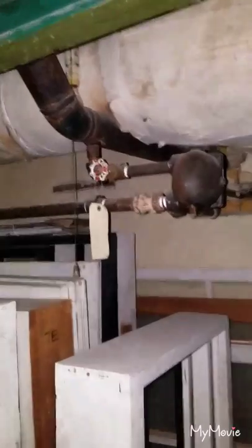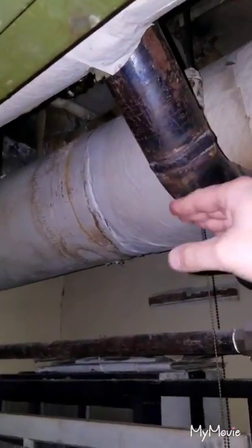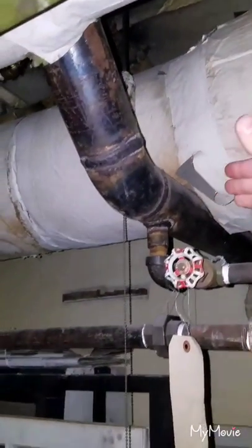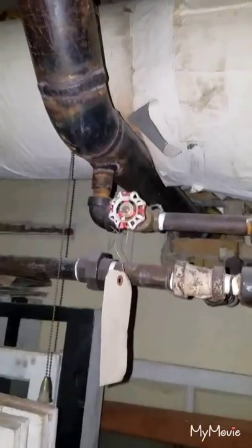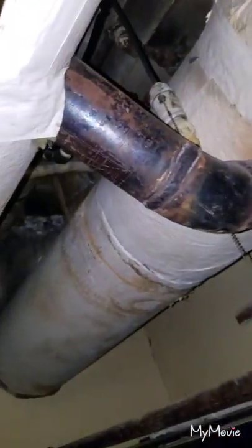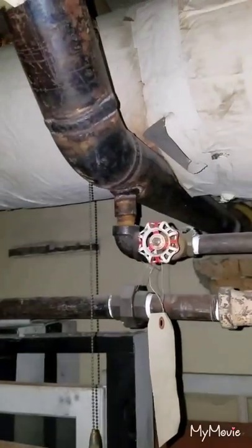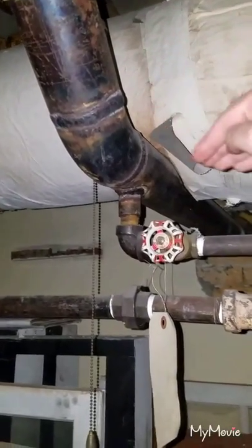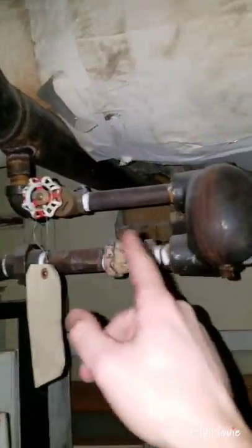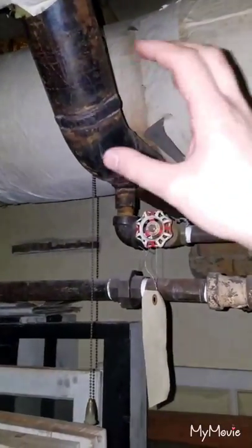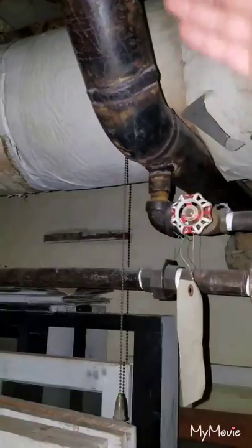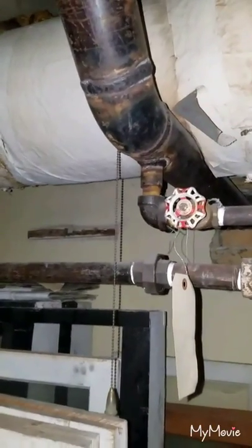All right, I'll take you to the next one to show you the bottom of a steam riser and a return riser. Okay, now it's also important to note, anytime you have a steam branch that has raw steam going through it that has to get to another area off of a main steam line, like this one here, and if it is below the main steam line and then goes back up, you need to have a trap off of it because condensate will collect and you can get damaging water hammer from that. So anytime it goes below its level, it needs a steam trap.